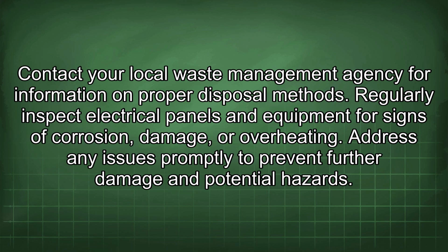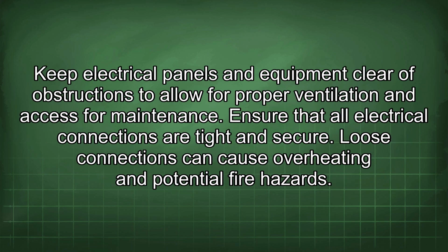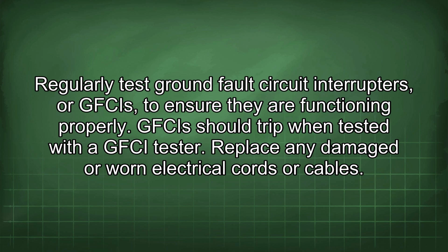Regularly inspect electrical panels and equipment for signs of corrosion, damage, or overheating. Address any issues promptly to prevent further damage and potential hazards. Keep electrical panels and equipment clear of obstructions to allow for proper ventilation and access for maintenance. Ensure that all electrical connections are tight and secure. Loose connections can cause overheating and potential fire hazards. Regularly test ground fault circuit interrupters, or GFCIs, to ensure they are functioning properly. GFCIs should trip when tested with a GFCI tester.